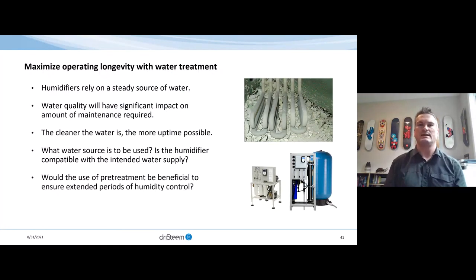So how do we maximize operating longevity with water treatment? Well, again, we need to look at the water source. We need to understand the water quality and what impact that could potentially have on the system. When there is cleaner water, so reduced minerals out of the water, there's more uptime or more operating time possible with the unit. And one of the other factors is what water source should be used. It depends upon the type of humidifier and the compatibility as well.